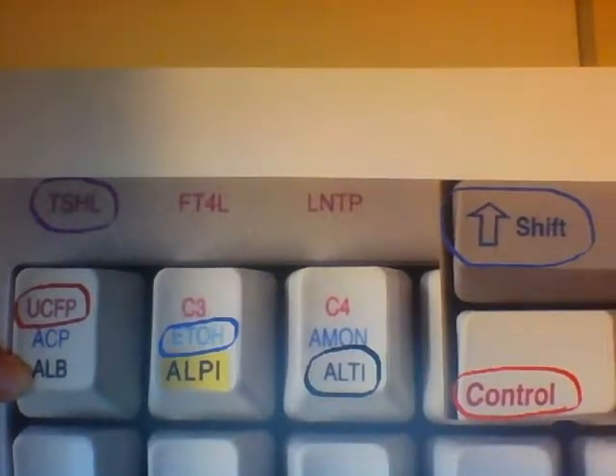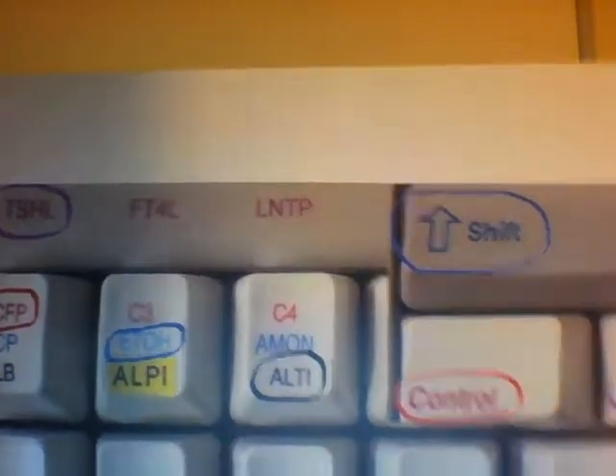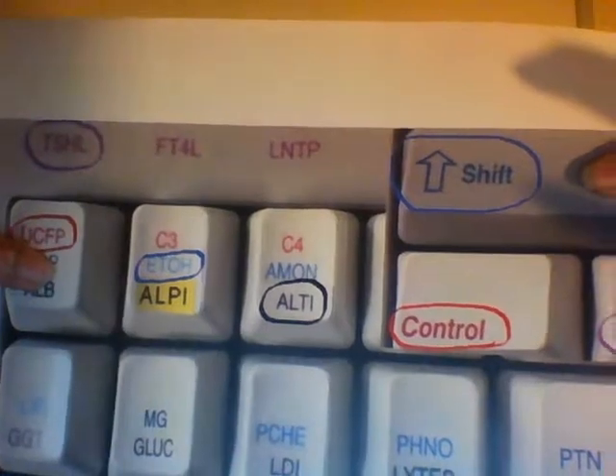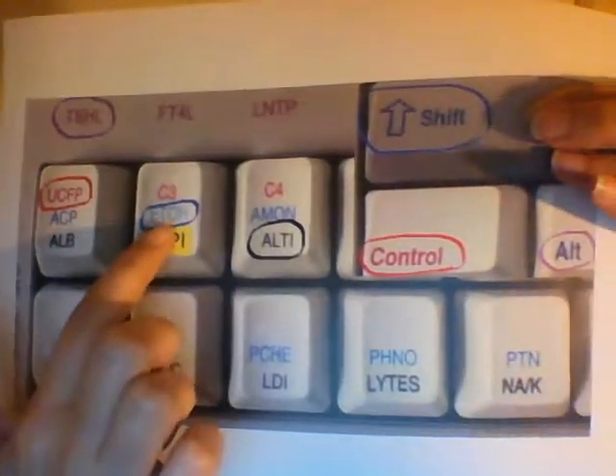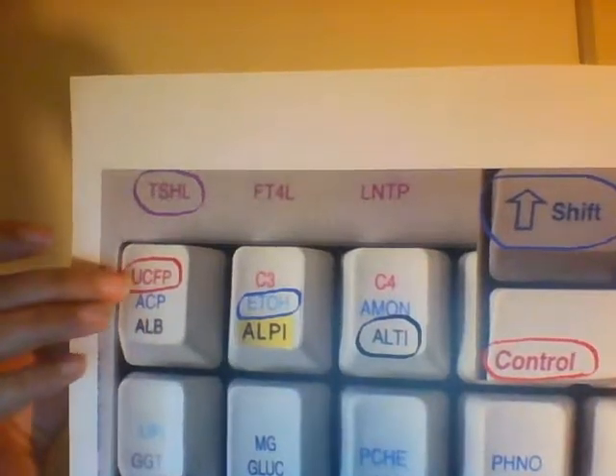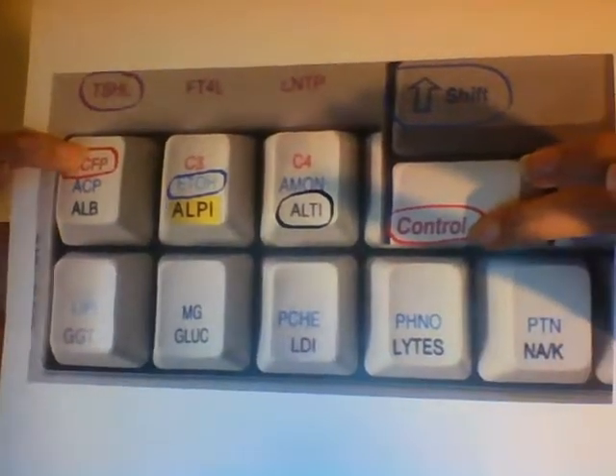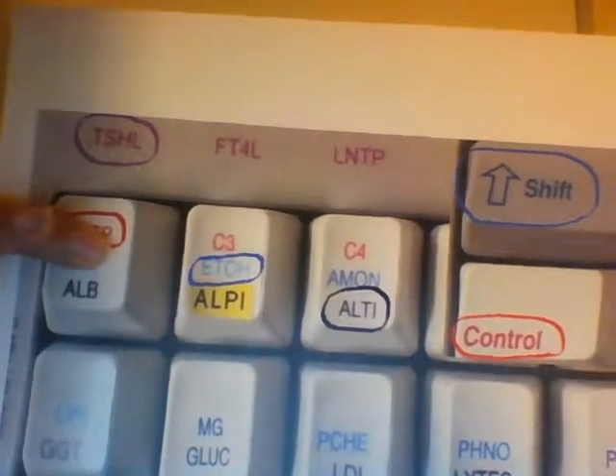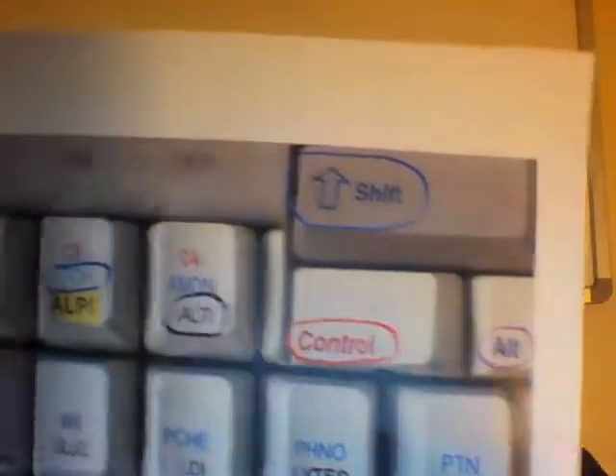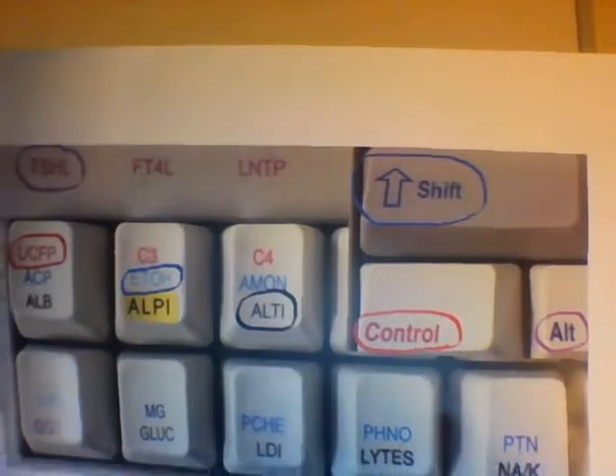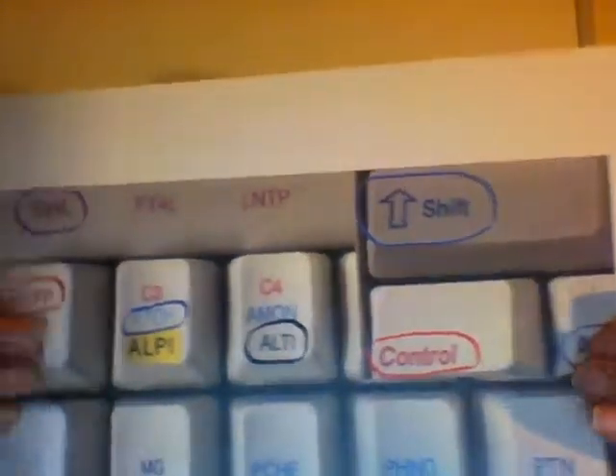Black means you can just touch the black method key and you don't have to do anything. For blue, you have to push the shift button right here along with the key that you want. So if you want ETOH, you push blue and ETOH. If you want UCFP, you push control, which is red, at the same time. If you want TSH, it's above this key, so you push this key with your ALT button, because the TSH is above this key. If you accidentally push the wrong method key, like you push albumin and you really want TSH, no big deal. Just push ALT and this key again and it will get the right method.